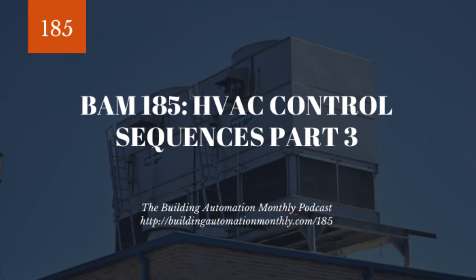So when we're dealing with economizer, a lot of folks will initially focus on what's called dry bulb temperature, which does not account for humidity. And that's all well and good in some climates, but if you're in the deep south of the US, that's not good because there's a lot of humidity. And with that humidity, you are introducing moisture into the system that cannot be removed by the system, which starts to heat up and make the spaces feel muggy. So when we're dealing with economizer control, typically we're going to look at dry bulb, which is just pure outdoor air temperature, and we're going to have an enable set point. And then we're going to let economizer control the discharge air temp. And if it doesn't meet discharge air temp, we're going to shut it back down to minimum position and start to enable the cooling coil.